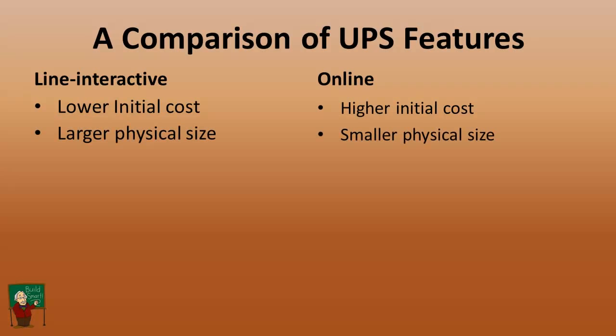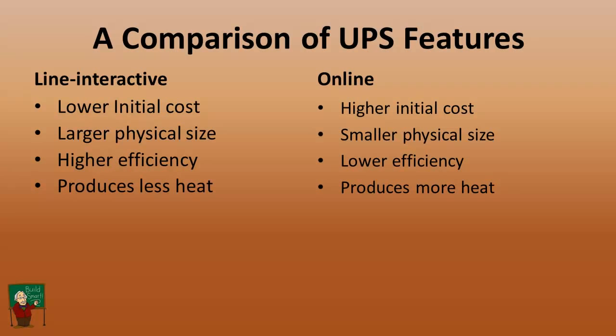The line interactive is typically larger physical size. The online would usually be somewhat smaller. The line interactive operates at a higher efficiency because most of the time the inverter doesn't have to operate. So it can charge the batteries up and then provide very little power consumption from the unit itself. It's just passing the power through. Because of the fact that it's doing less during normal operation, it produces less heat as part of that efficiency.